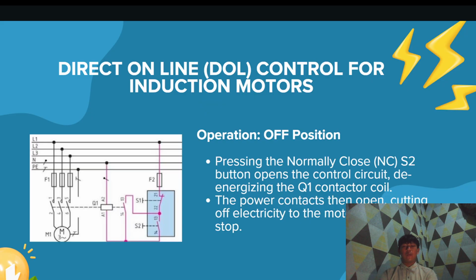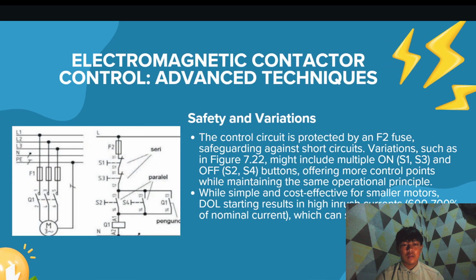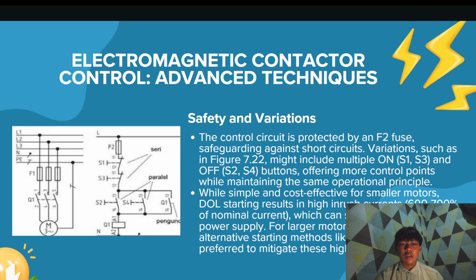Operation in the off position. Pressing the normally closed, or NC, S2 button opens the control circuit, de-energizing the Q1 contactor coil. The power contacts then open, cutting off electricity to the motor, causing it to stop. Safety and variation. The control circuit is protected by an F2 fuse, safeguarding against short circuits. A variation such as in figure 7.22 might include multiple on buttons S1 and S3 and off buttons S2 and S4, offering more control points while maintaining the same operational principle.